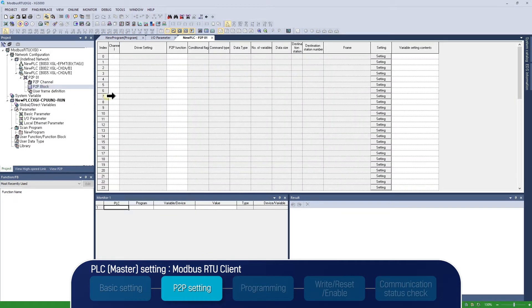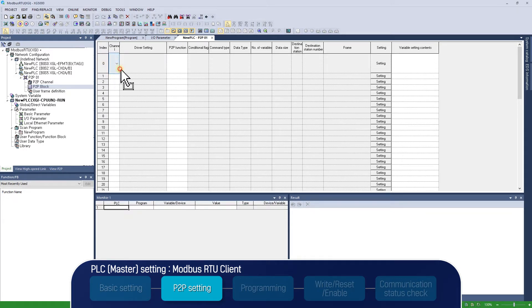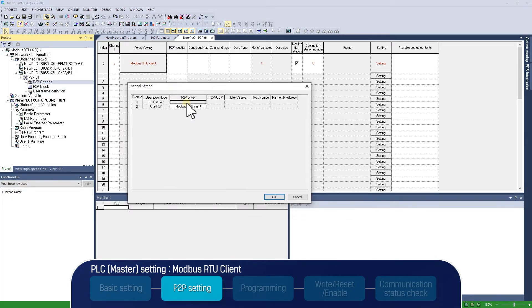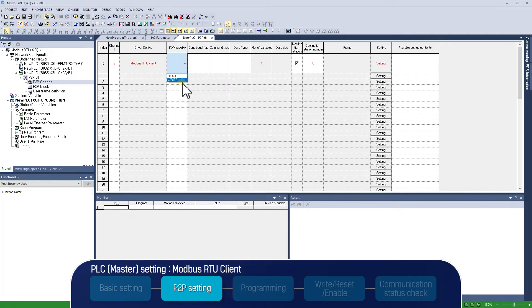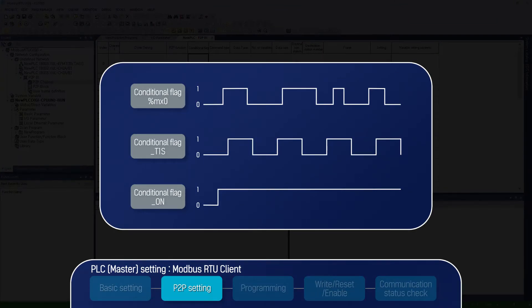P2P Block setting is required after P2P Channel Setup. P2P Block is a group of indices, and each is a communication message. As PLC sends one write request to the drive, we are going to edit one index. Select 2 in Channel of Index 0. Modbus RTU Client appears automatically in Drive Setting field, as we set Modbus RTU Client in P2P Driver of Channel Setting. We will select Write in P2P function, as PLC sends a write request to the drive. Conditional flag is very important. When this flag bit turns on, its index will be transmitted to the dedicated server. CNET Communication module sends the index when the conditional flag bit status changes from 0 to 1.